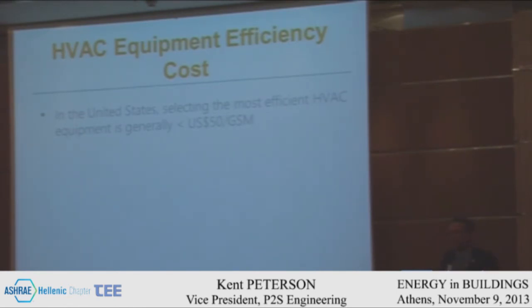It's interesting that sometimes we get lost in the cost of energy efficiency. Two years ago, the U.S. General Service Administration, the largest owner of building stock in the United States, commissioned me to evaluate the true cost of going to the highest level of energy efficiency on an office building versus the minimum code-required efficiency. Believe it or not, it was only $50 per gross square meter to reach the highest level of efficiency available on the market today.